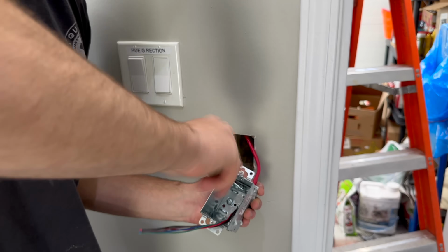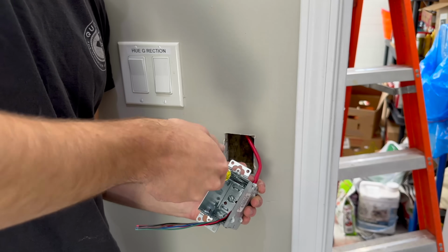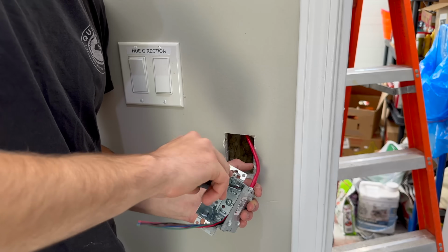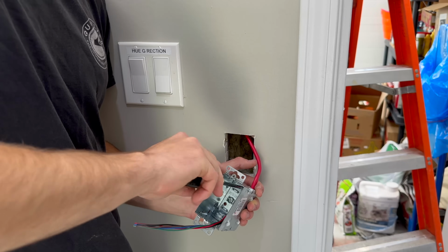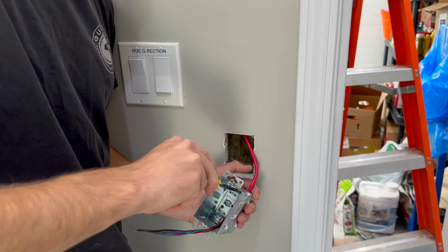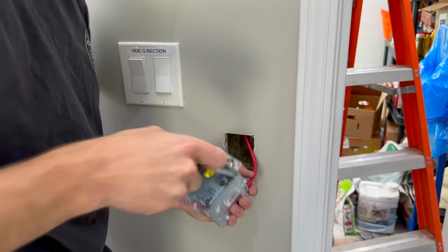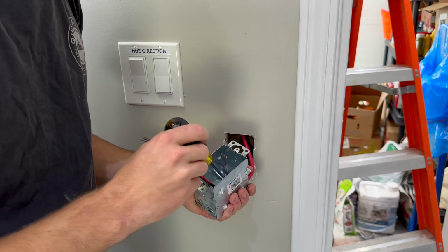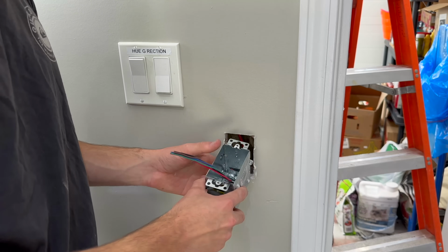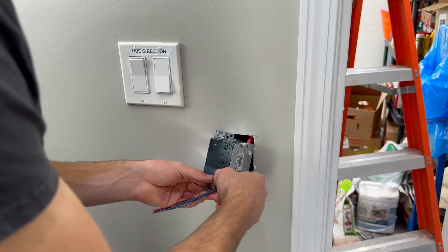Now this is a 5 conductor because I maintain a loop system. I don't T-tap. T-tapped systems are a nightmare to try and work on. You always want systems to be wired in a loop. Class A is ideal, but this building was a retrofit system, so Class A isn't always practical to be done. You can see that's snugged up on there, but not crushing the insulation down. So I can now put this in the wall.